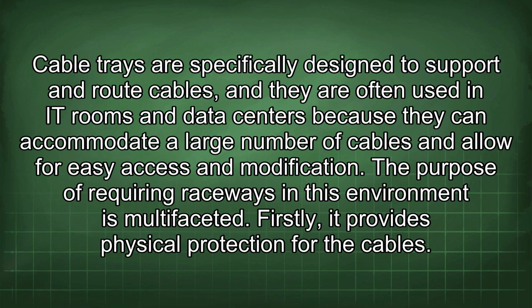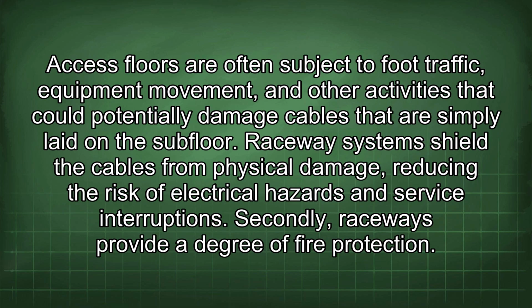trays. Cable trays are specifically designed to support and route cables, and they are often used in IT rooms and data centers because they can accommodate a large number of cables and allow for easy access and modification. The purpose of requiring raceways in this environment is multifaceted. Firstly, it provides physical protection for the cables. Access floors are often subject to foot traffic, equipment movement, and other activities that could potentially damage cables that are simply laid on the subfloor. Raceway systems shield the cables from physical damage, reducing the risk of electrical hazards and service interruptions.